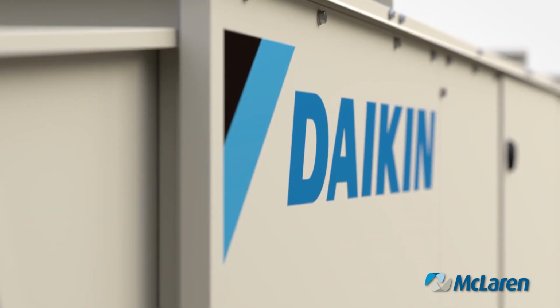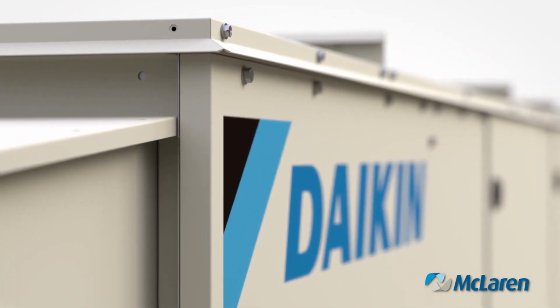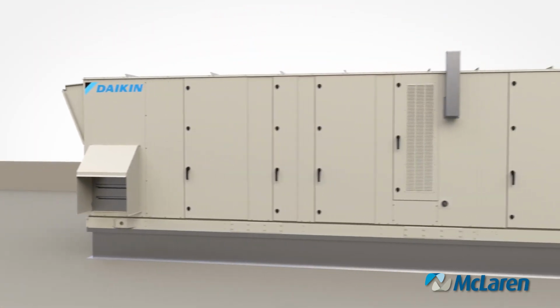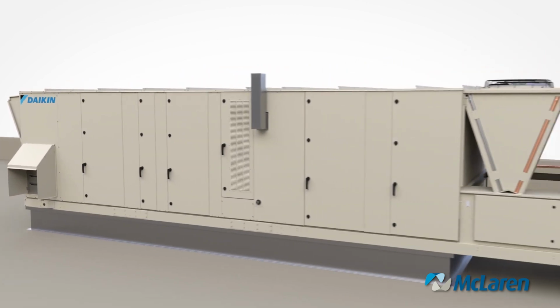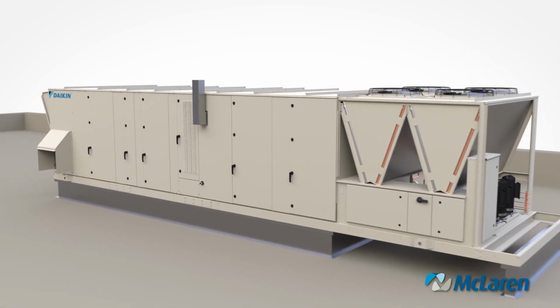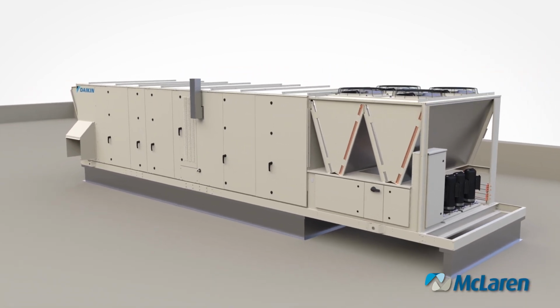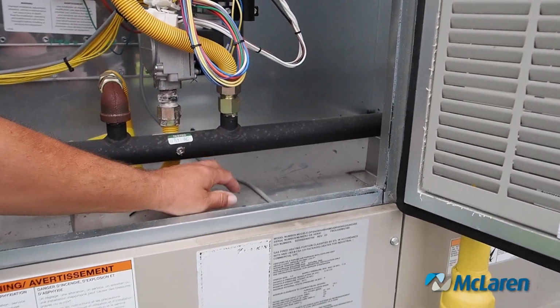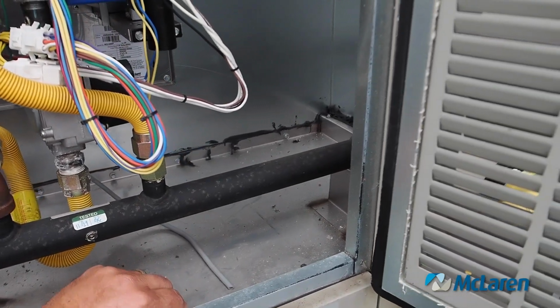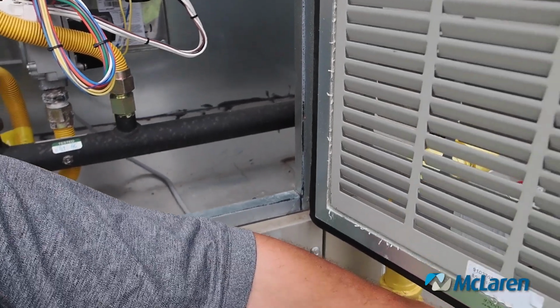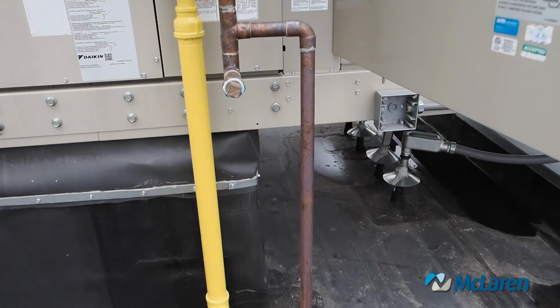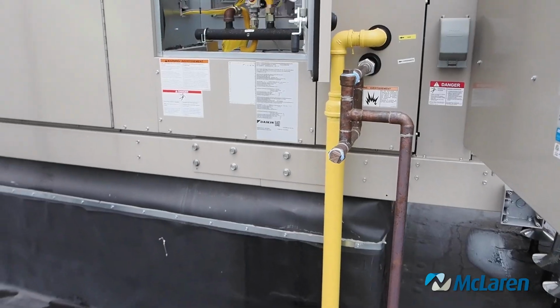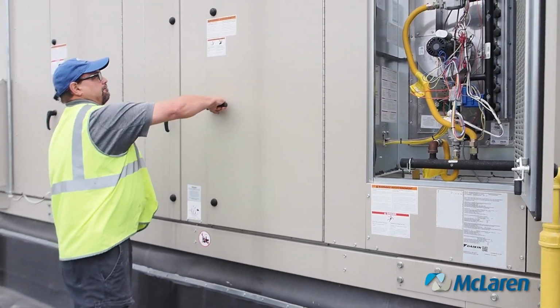The motor here is a non-maintenance motor. There's no grease or bearings or anything. There are bearings, but there's nothing to oil or maintain. This does condensate. If you want to come on here really quick, you will see condensation pile up in here, and eventually, if it gets bad enough, it will drain out this copper drain here. There's no pressure on that water, it's just gravity. Moving on to the next section.